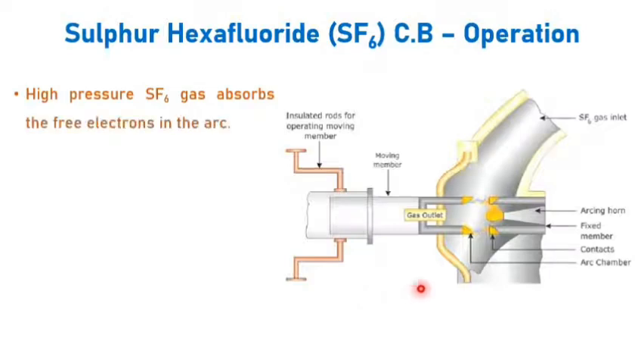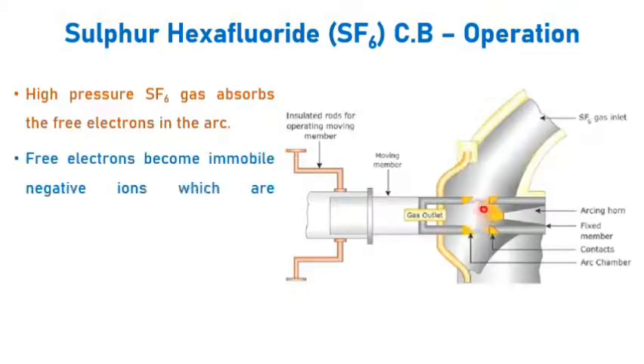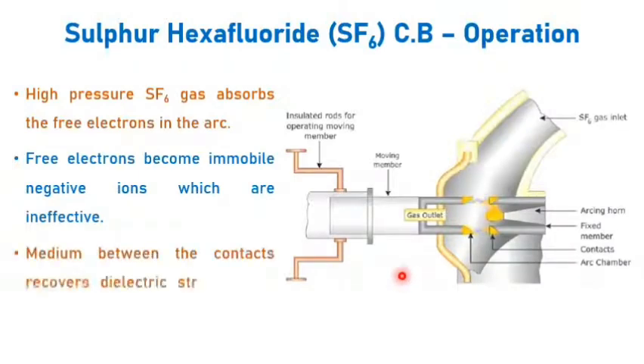Now this high pressure SF6 gas will absorb the free electrons that are present in the arc. So the free electrons become immobile negative ions. Immobile means they cannot move freely from one point to the other. Therefore the current cannot flow through the gap between the contacts. Hence the medium between the contacts recovers its dielectric strength at a faster rate and the arc can be extinguished. When the medium recovers its dielectric strength faster, deionization happens and the arc cannot restrike further.